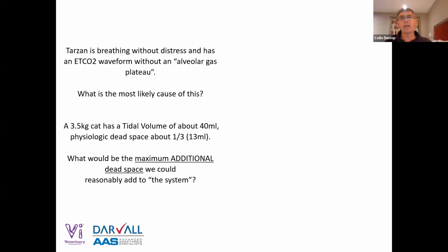If we have an unsealed endotrach tube or the cuff isn't sealed, when the cat breathes in and out, some room air gets in there and that can damp out the signal. And finally, the cat itself doesn't have that big of a tidal volume, although this cat's a decent sized cat. And depending on how much equipment dead space we add to that, that could cause us not to get an alveolar gas sample. So all of those things could do it.